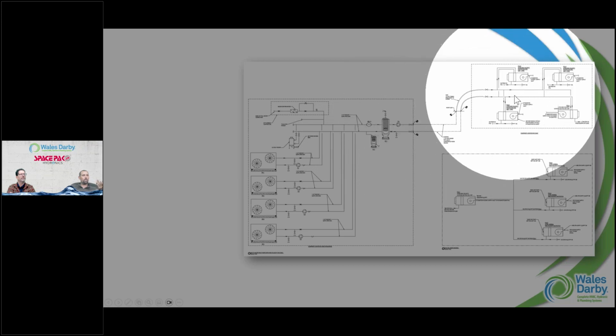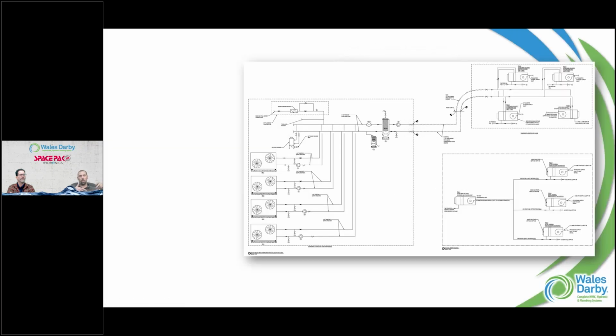It doesn't look like a reverse return—no, so they staged these outdoor units. We go through, so there's my hydraulic separator, and then here's my system side. In this box there are 4 air handlers, so it's 4 high velocity units. They put circuit setters on each air handler so that the one circulator over here, when that thing's on, it's going to provide the right amount of GPM through each air handler, so we get the BTUs. This isn't, you know, think about maybe a high residential home where we have multiple outdoor units satisfying the buffer tank, and then all these zoned air handlers or radiant heat—there can be really anything there.